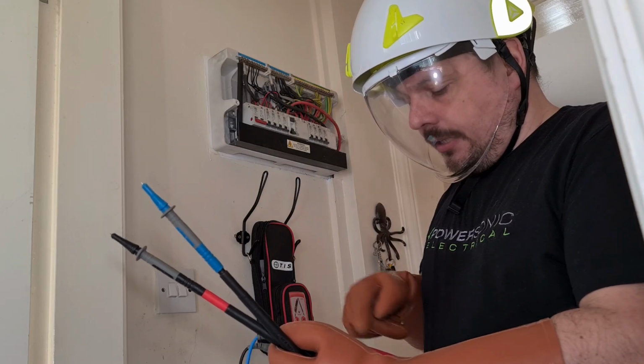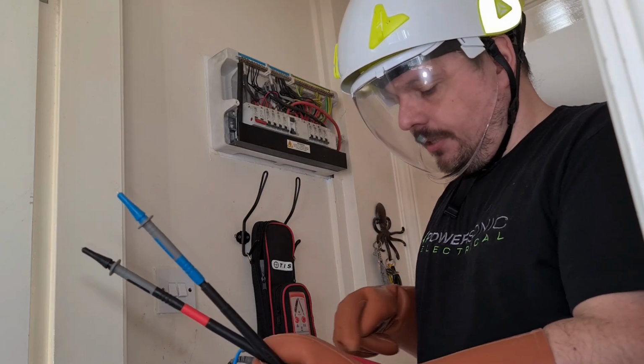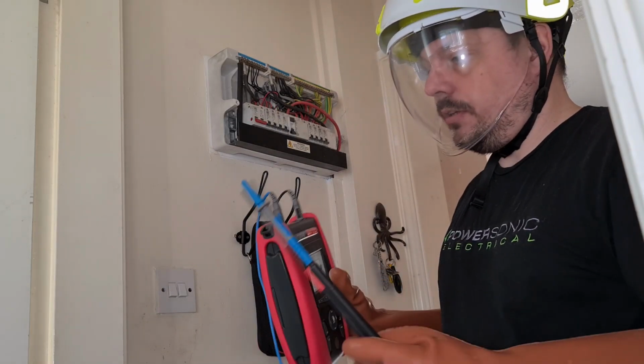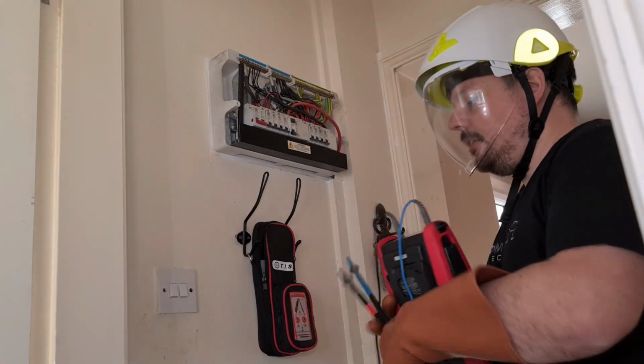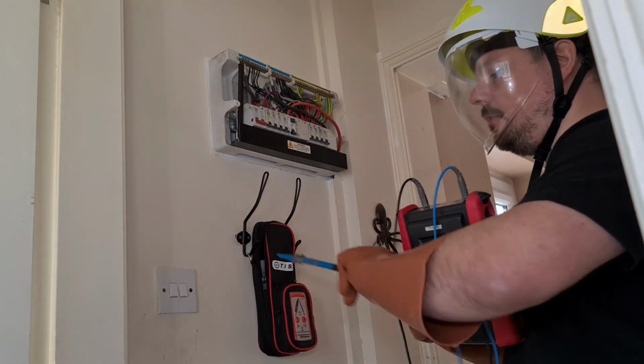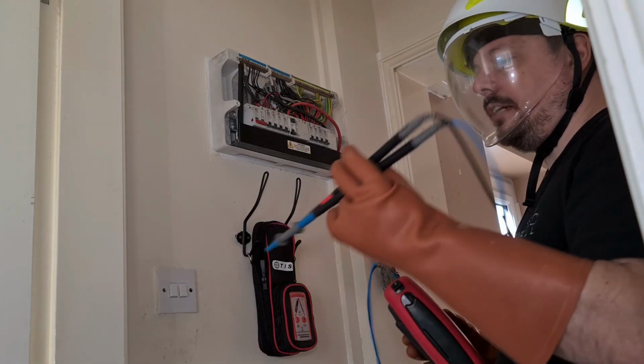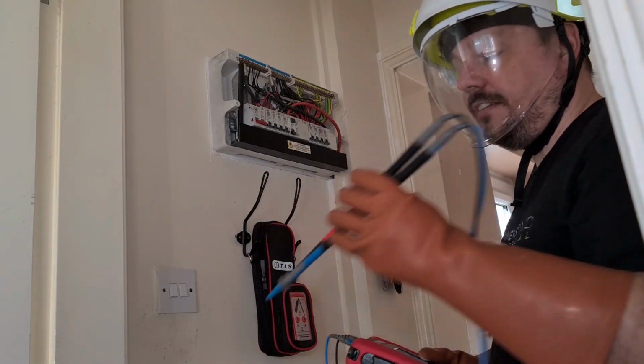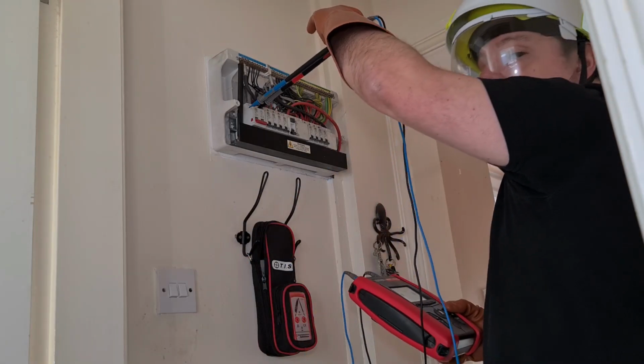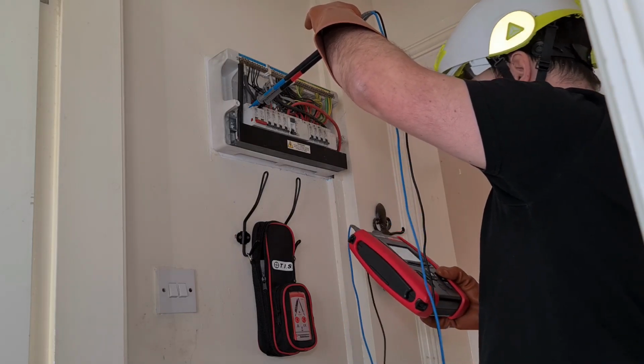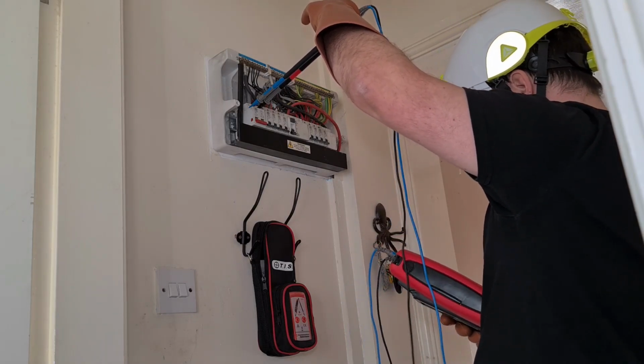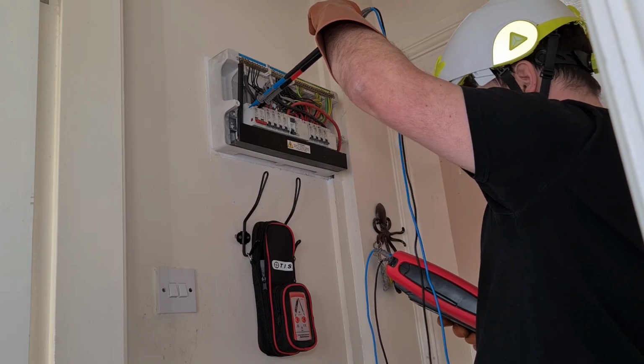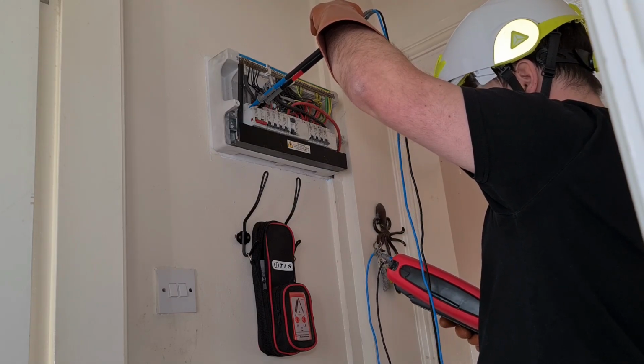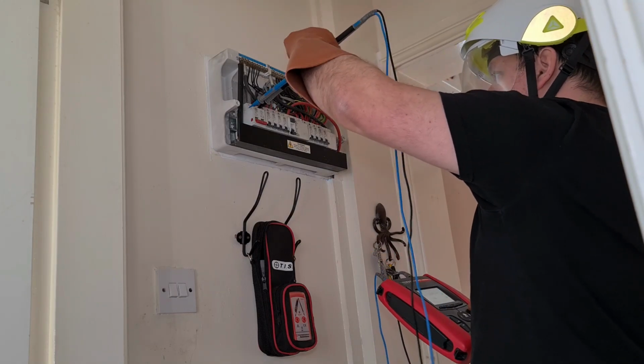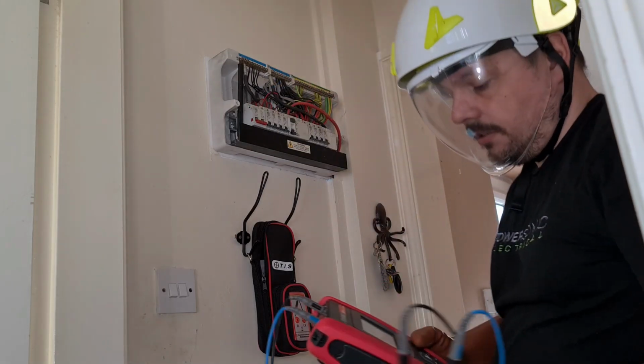So we want to be on the loop impedance, make sure we're between line and neutral, we've got the probes connected in. Now with this I'm using the long reach probes, just to try and keep myself at an extra especially safe distance. So with these two extended probes we're going to make sure we're on the terminals. I'm not going to hang about here because obviously I'm inside a live enclosure. And I'm happy with that.